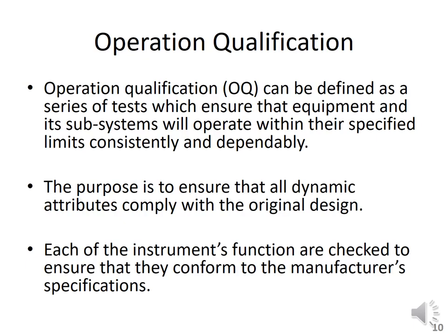Okay, so each of the instrument's functions are checked to ensure that they conform to the manufacturer's specification. This is important. If you confirm the proper functioning of the machine beforehand, in the long run you are not going to face any difficulty, and it will be working smoothly and nicely.